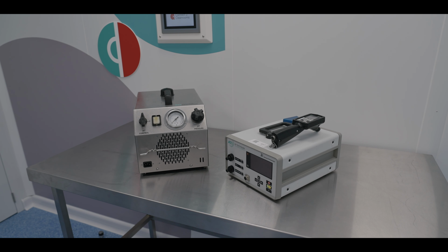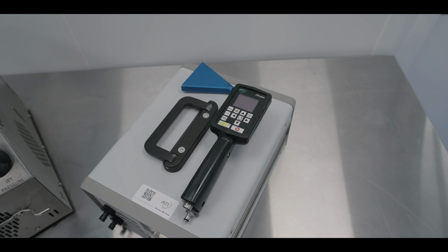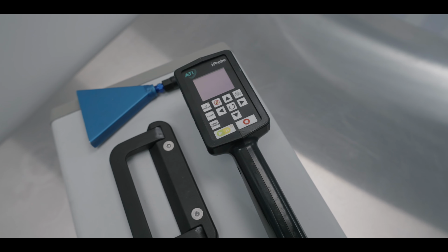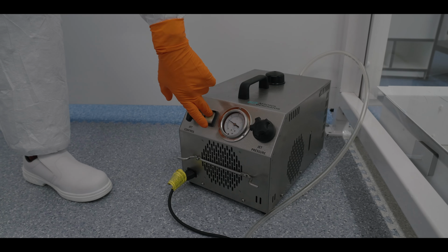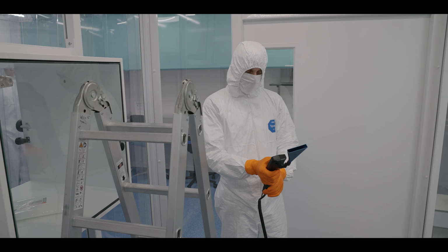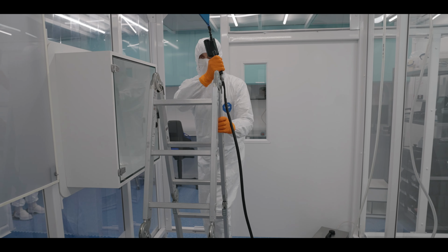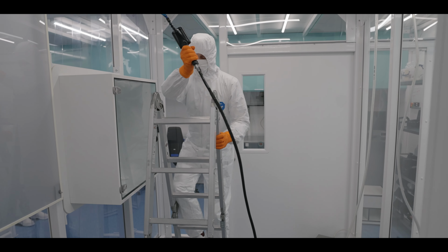In this test we'll be looking at DOP filter integrity. The filter integrity test in a cleanroom, often referred to as a DOP test or filter leak test, verifies that the filtration system, usually HEPAs or ULPA filters, are properly installed and functioning correctly, and ensuring they are effectively removing airborne particles.